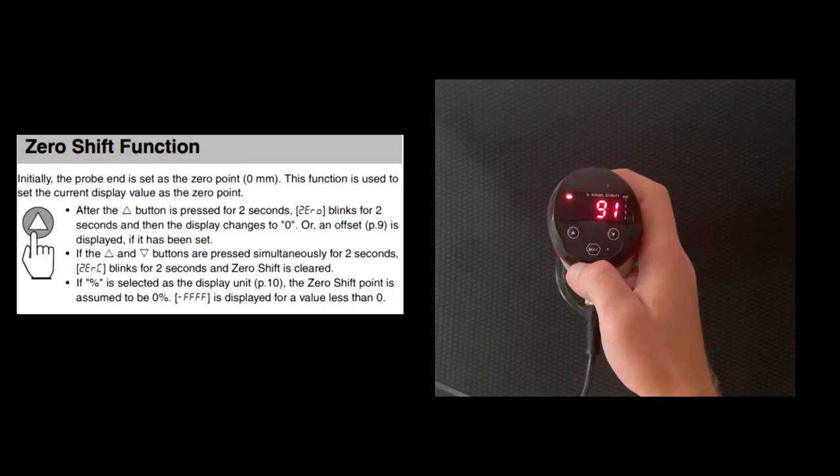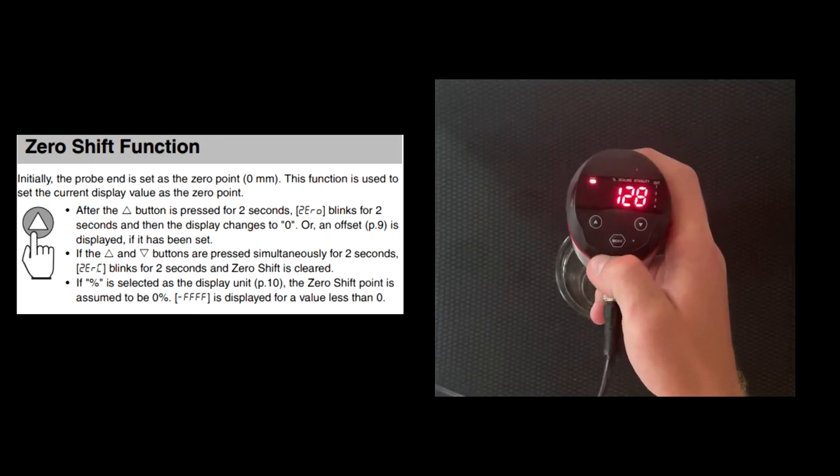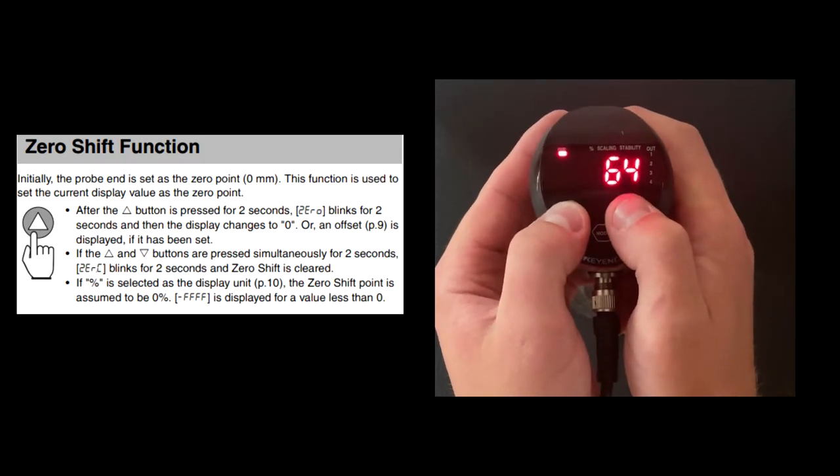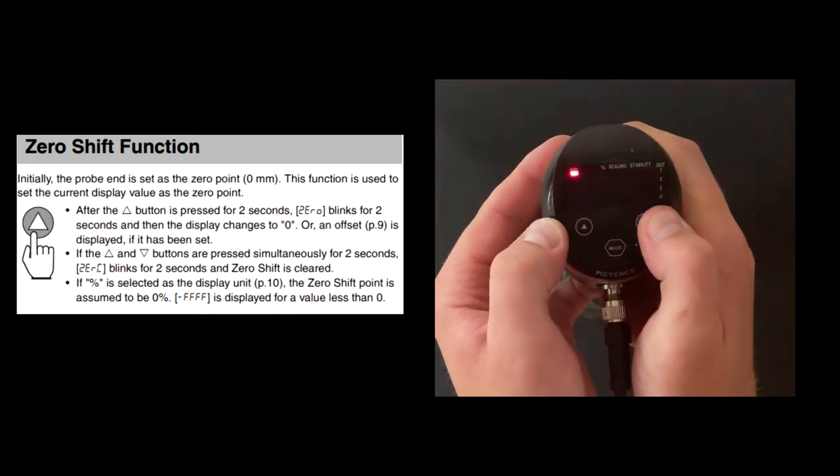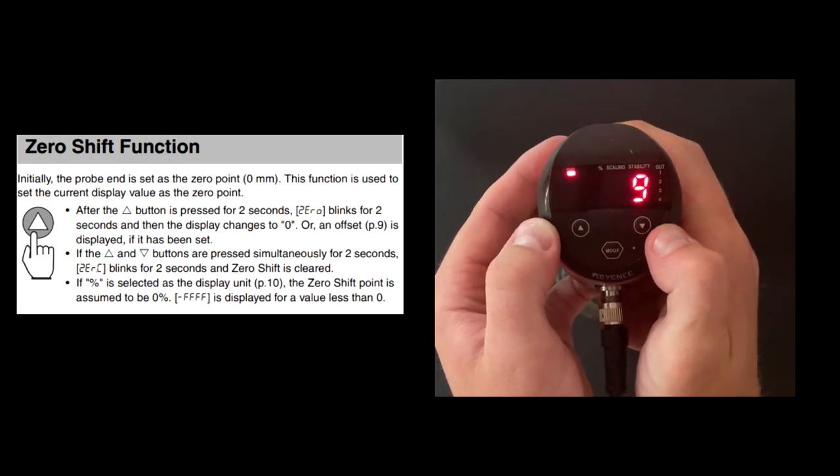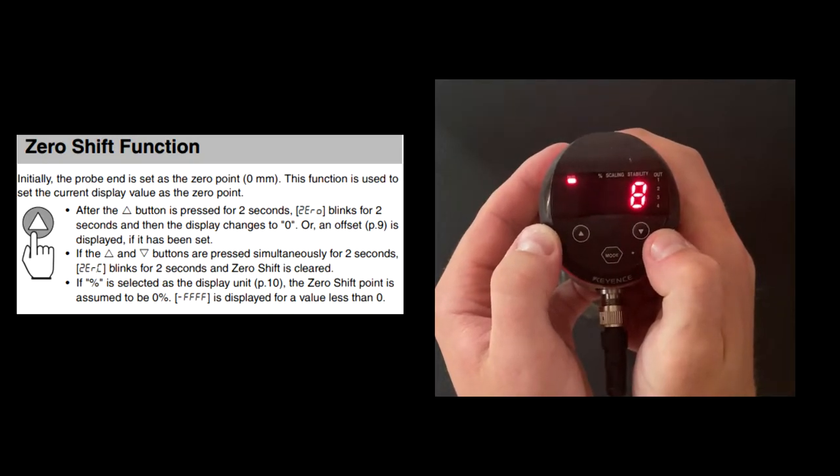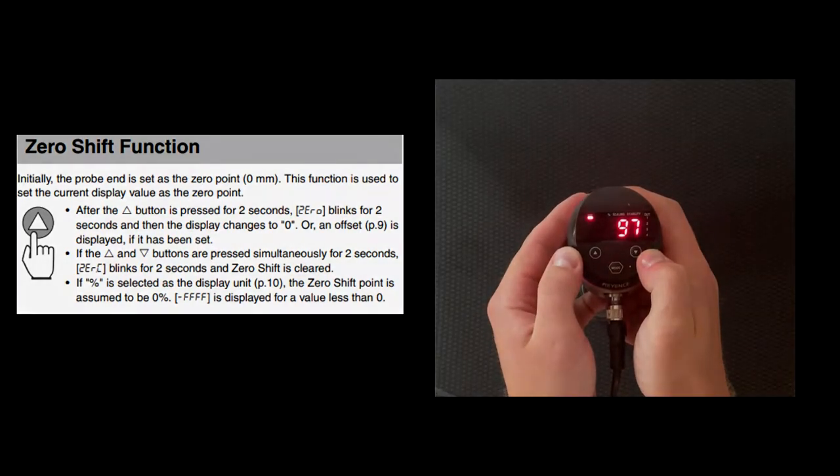Our next recommendation is to perform a zero shift. To do this, you want to maintain stability on the main display screen. Place just the tip of the probe into the liquid and hold the Up button until ZERO flashes on the screen. This will be a successful zero shift, and now the tip of the probe will be calibrated for zero millimeters.